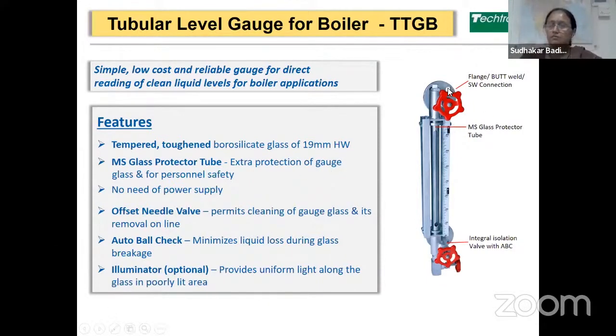Then it has a process connection, which can be available in flange connection, butt weld connection, or screwed or socket weld connections. As a mechanical gauge, this doesn't require any power supply. Then the end block consists of an integral offset needle valve, which is provided with the ABC ball check valve, used for minimizing the liquid loss during glass breakage. Optionally, this is also provided with an illuminator to provide uniform light along the glass in poorly lit areas.